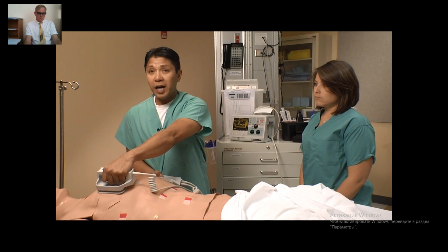If your patient needs to be shocked, turn the dial clockwise and select defib. The individual assisting must be informed of the desired energy level. 360 joules, please. Push the energy button until the desired energy level is selected. Then push the charge button. A low-pitched noise will occur, alerting you that it is charging to the desired energy. A high-pitched noise will then sound once it has reached the desired energy level.